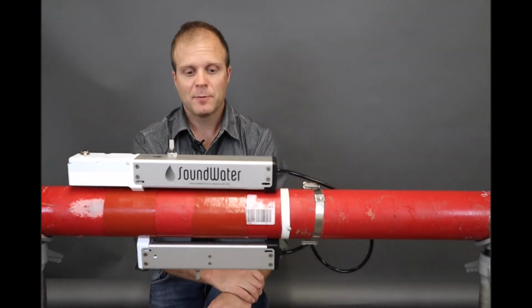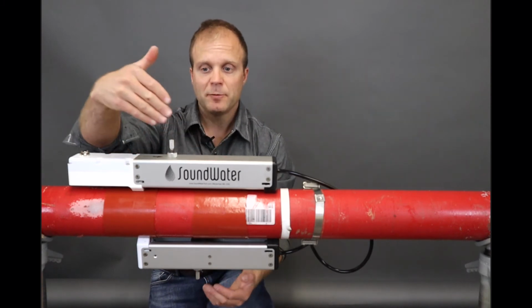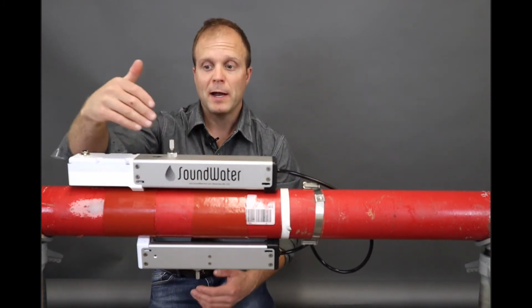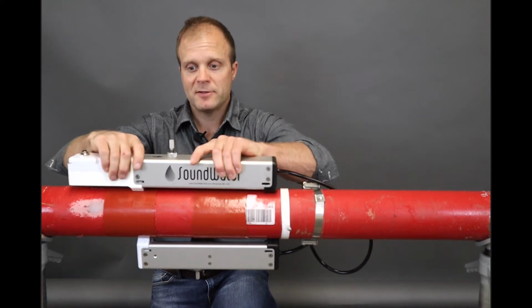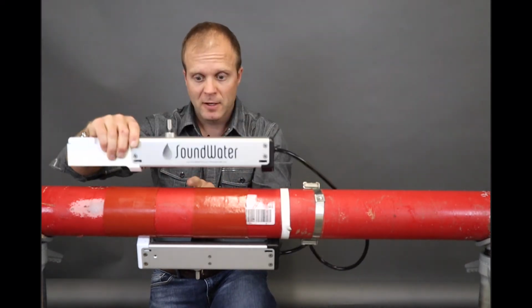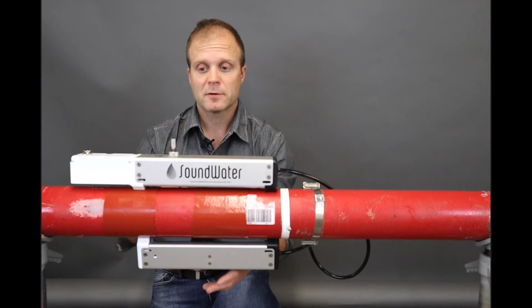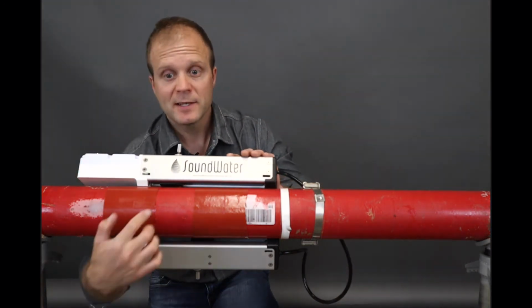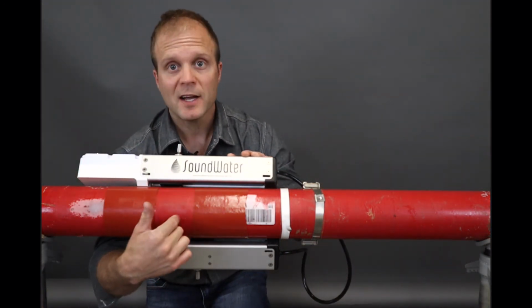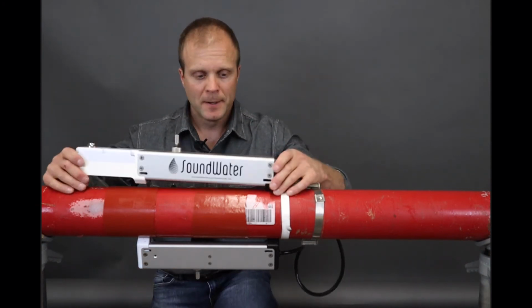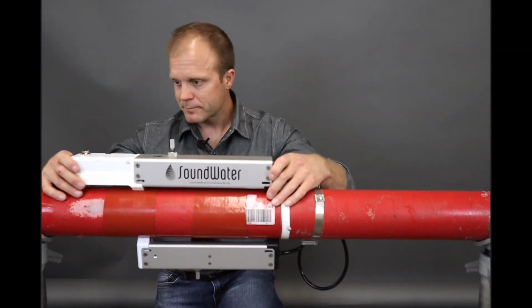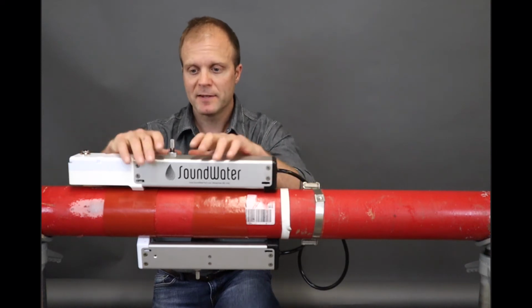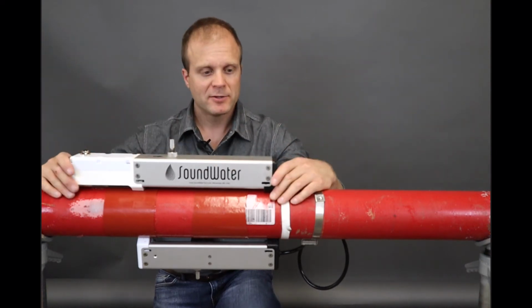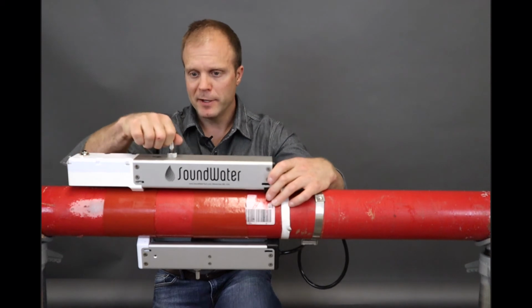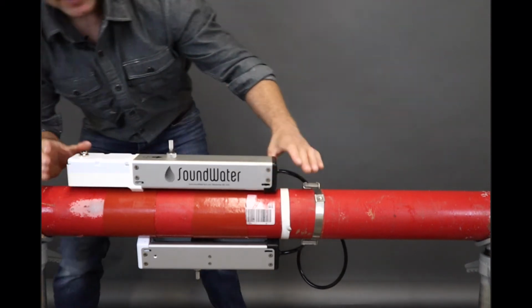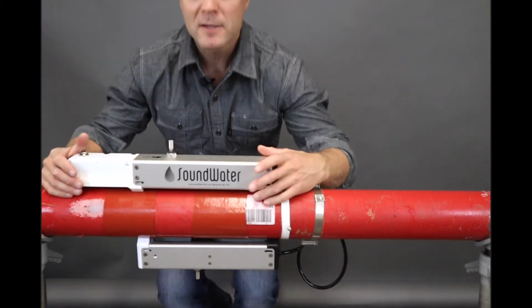Okay, next important thing is these halves need to be 180 degrees apart on the pipe. Why? Because the sound has to transmit from one transducer into the pipe and hit the receiver. So if it's off to the side, the sound's going to shoot through and come out somewhere on the side here and not hit this receiver. So you don't have to be super exact. The sound is sort of a beam, so there's plenty of slop, but do your best. So I'll just look from the side. Okay, great, looks about 180 degrees apart.